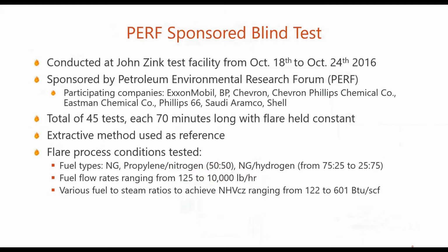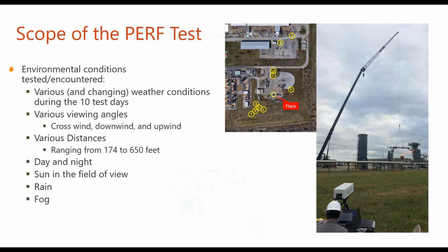And I should mention this test was completely blind. So the fuel type, fuel flow rate, and steam ratios, none of this was provided to the participants. They were asked to provide the combustion efficiency blind without knowing anything about the process conditions. As I mentioned, this test covered 2 weeks, so we were exposed to a variety of environmental conditions and different temperatures. Tests were done during the daytime and nighttime.